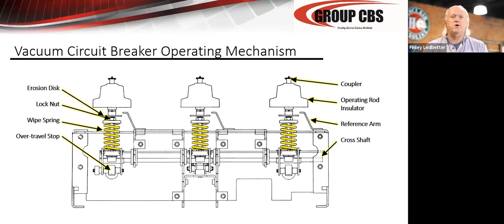That should be part of a major maintenance, a major overhaul that should happen at about 3,000 operations with most air breakers and vacuum breakers, particularly this GE breaker here that we're talking about, which has a tremendous amount of force. This breaker produces about 1,200 foot-pounds of force onto the vacuum interrupters. It's a very big, strong mechanism.